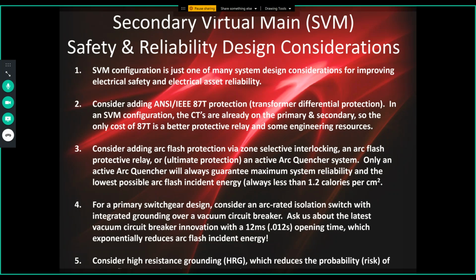And in a secondary virtual main construction, of course, that has a dramatic effect. In most of my models, at least an 87% reduction or more in secondary arc flash incident energy when you compare a 12 millisecond opening time primary breaker to one that takes 50 milliseconds to open. And by the way, 50 milliseconds is considered a modern fast breaker. There are many vacuum breakers out there which are still 5-cycle or 83 millisecond opening time breakers. So this 12 millisecond breaker is really a game changer in terms of arc flash mitigation, especially when used with secondary virtual mains.